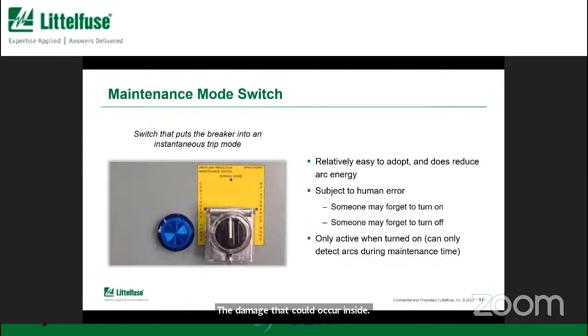Another thing you may see is that on different types of circuit breakers, they have what is called a maintenance mode switch. This is a manual switch where you can put the breaker into maintenance mode. And really, that turns the overcurrent into a very fast-acting, instantaneous trip. So anytime there's a blip of current that goes above the rating, the breaker will react very, very quickly. So it does reduce the arc energy. But the issue here is that it is subject to human error. What if somebody forgets to turn the switch to maintenance mode, and then they open the door and do their work? The energy has not been reduced. The other thing that can happen is they could leave it on accidentally.